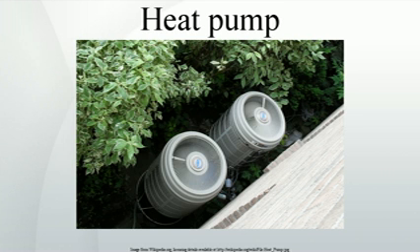Ground source heat pumps are simpler and more reliable than air source heat pumps. They do not need fan systems or defrosting systems and can be housed inside, but the need for a ground heat exchanger requires a higher initial capital cost in exchange for lower annual running costs, as well-designed ground source heat pump systems enjoy a more efficient operation. Heat pump installations may be installed alongside an auxiliary conventional heat source such as electrical resistance heaters, or oil or gas combustion. The auxiliary source is installed to meet peak heating loads, or to provide a backup system.